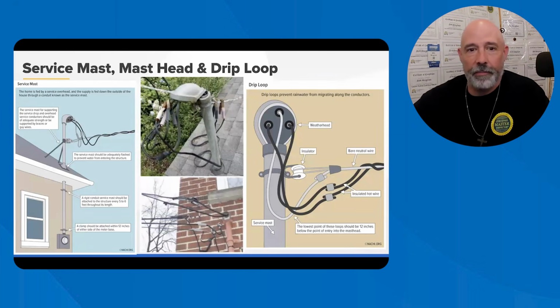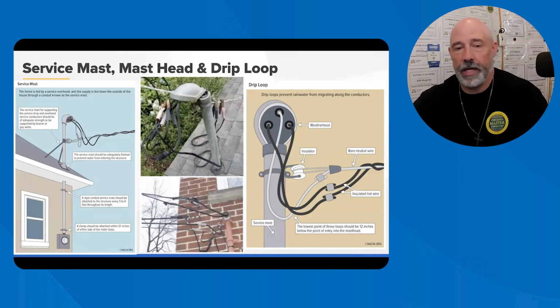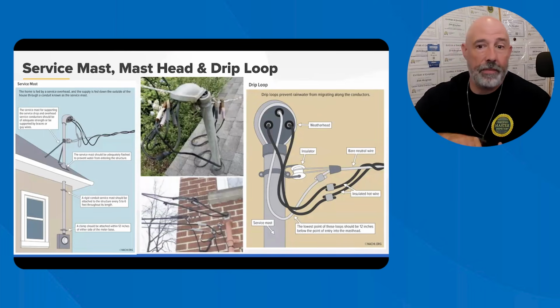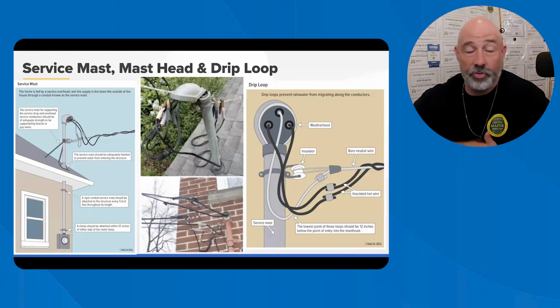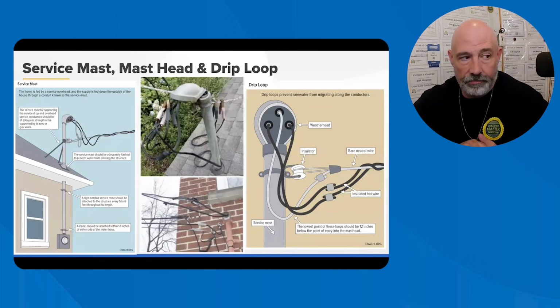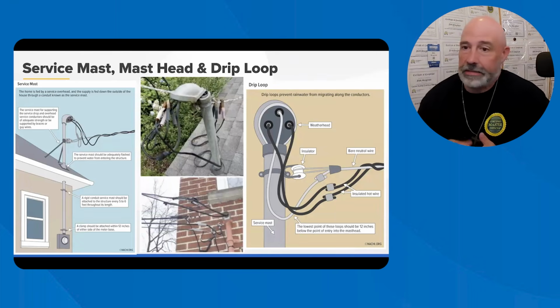Couldn't believe it. But this allows the water to drip off those conductors. So even if you're hanging up your Christmas lights, things like that, you use that. It works very well. Inspectors should look for damages, loose fittings, anything that looks outside the normal. Make sure that you're calling those out. Missing those drip loops. I've seen it where they forgot to put them in, and it just goes straight into it. Like, that's not good. Yeah, not good.